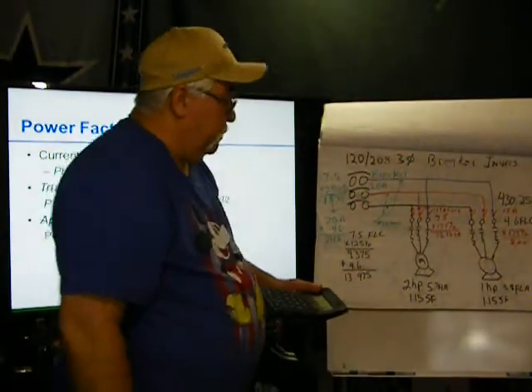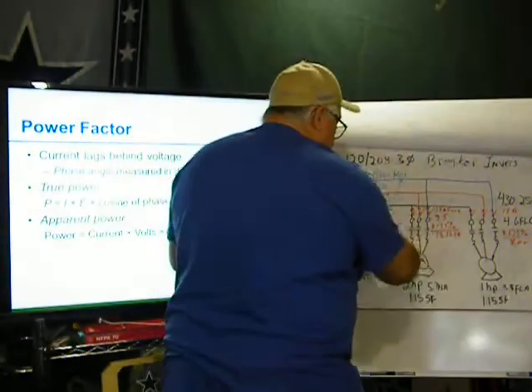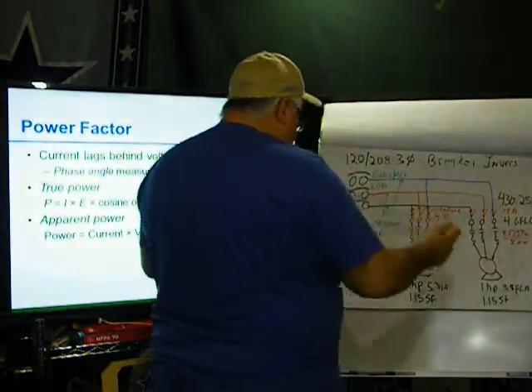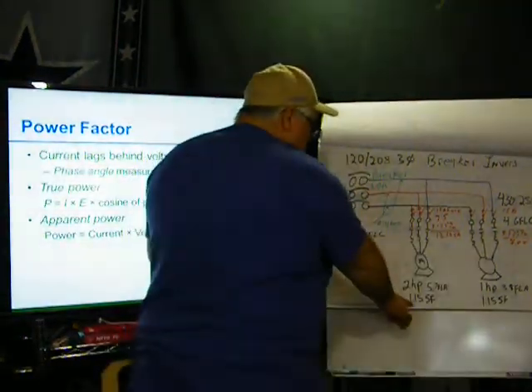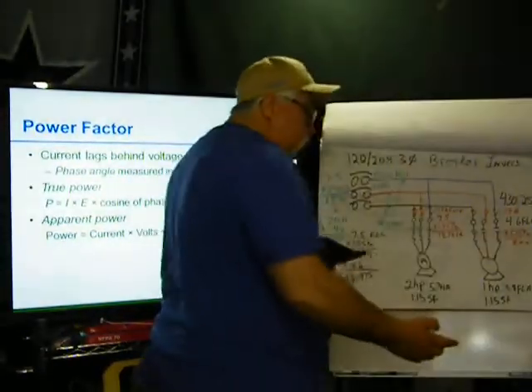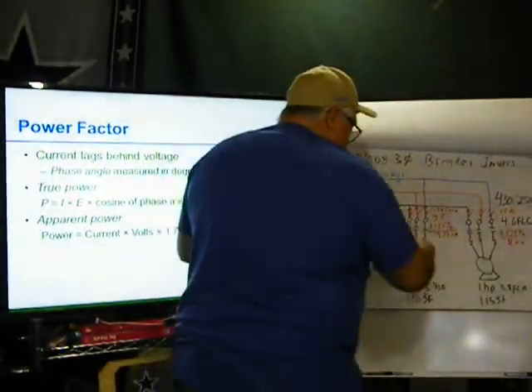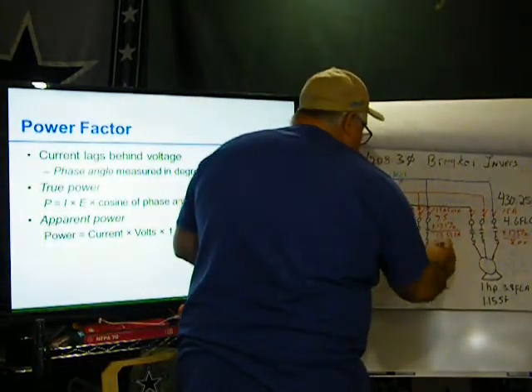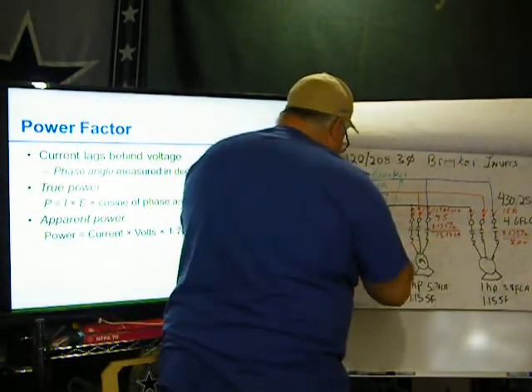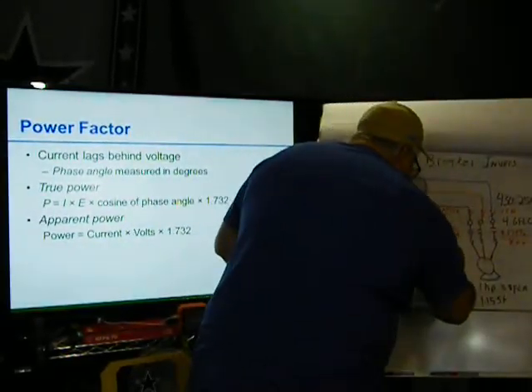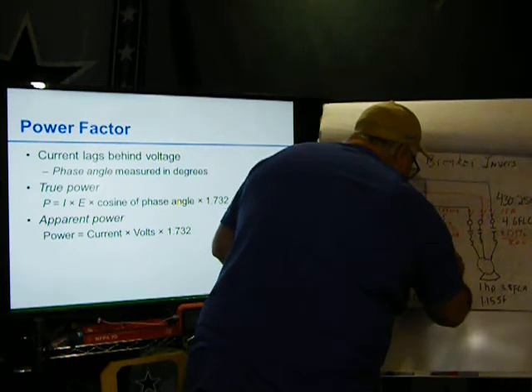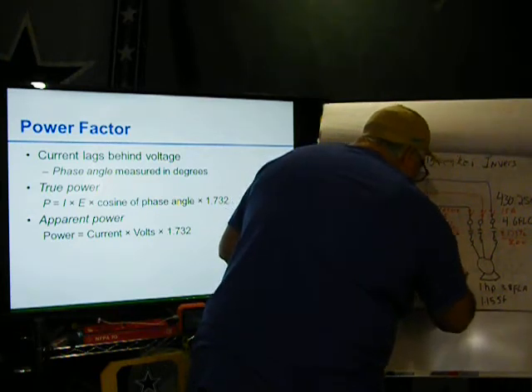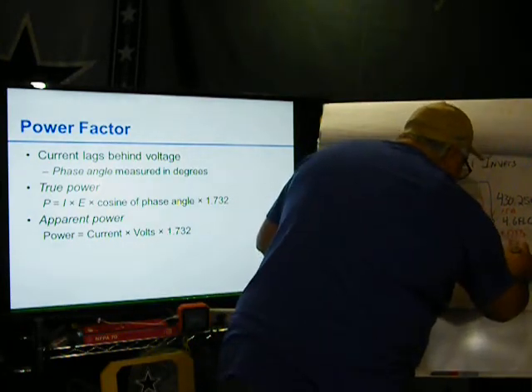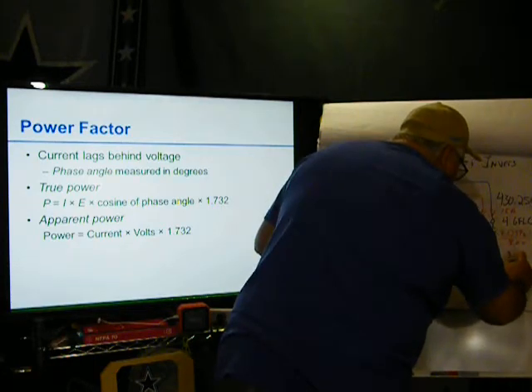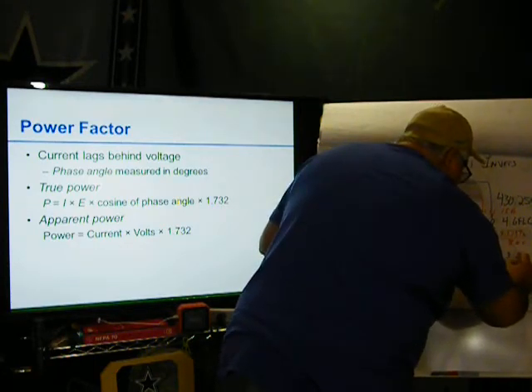Okay, we do our overloads. Our service factor, I didn't give you a service factor, well here it is, 1.15. That's why I gave you the service factor, so you could find the overloads. So again, now we're going to use the nameplate. So 5.7 times 125%. Okay, 3.8 times 175%, 125%, I'm sorry.